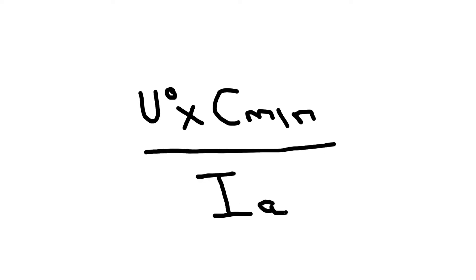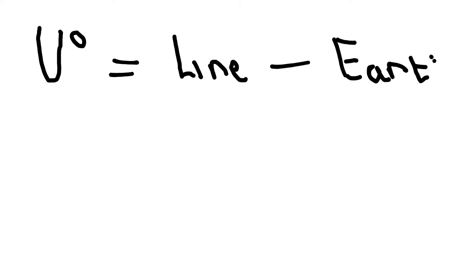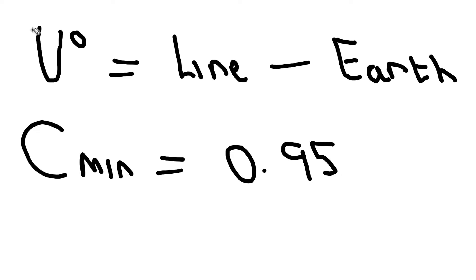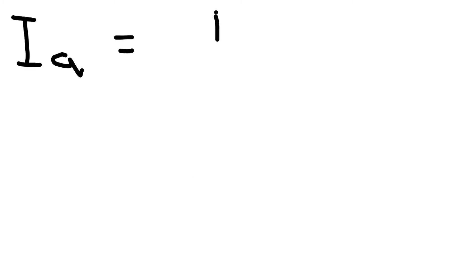Using this formula is dead simple. Just to clarify before we begin, there's a few things I need to explain. The first is C-Min. Some of you might have come across it before, but C-Min is a correction factor - it's the minimum voltage factor to take account of voltage variations depending on time and place, changing of transformer taps, and other considerations.